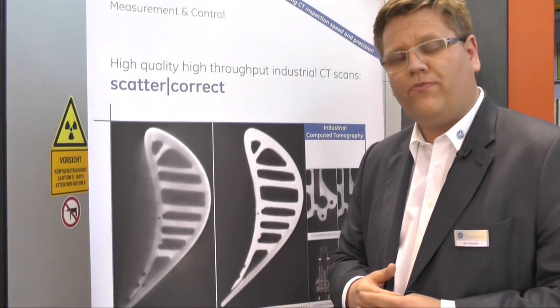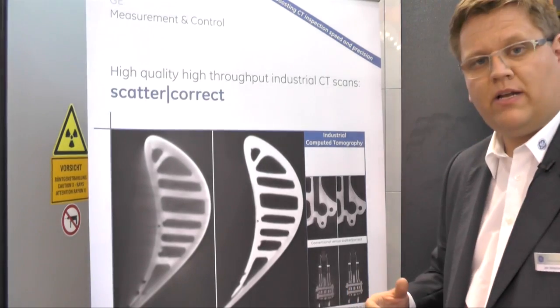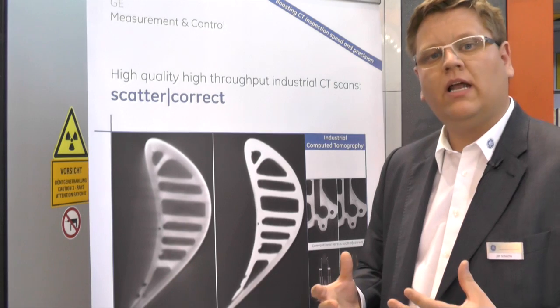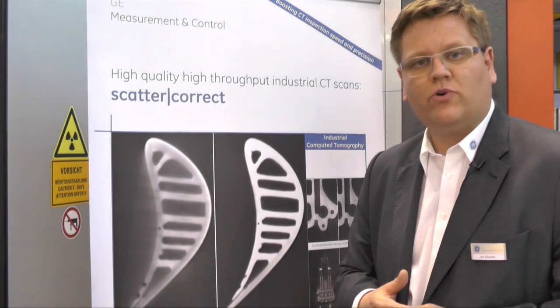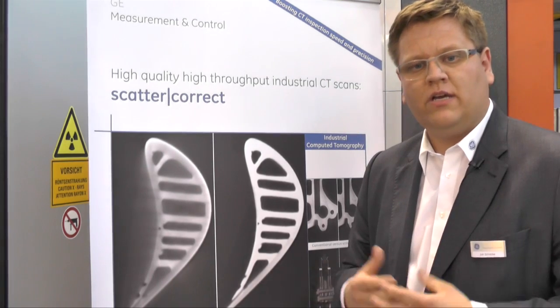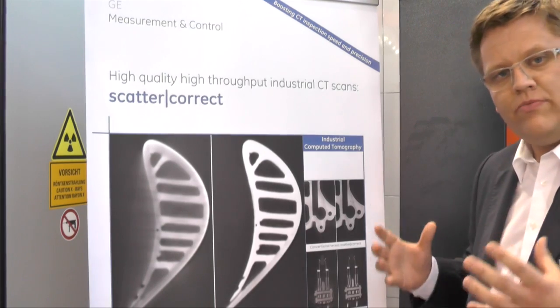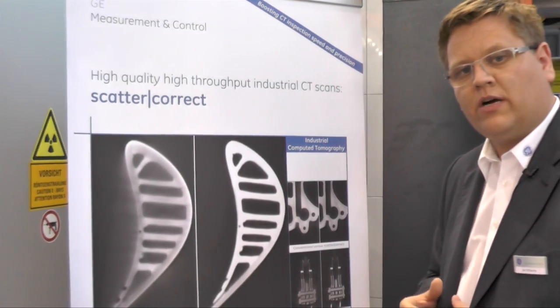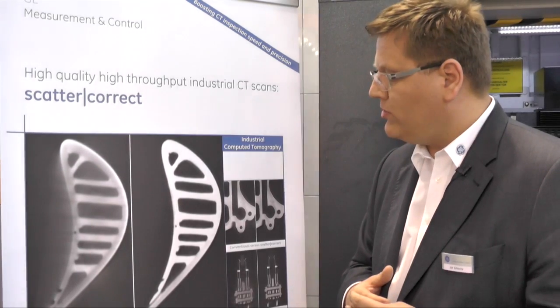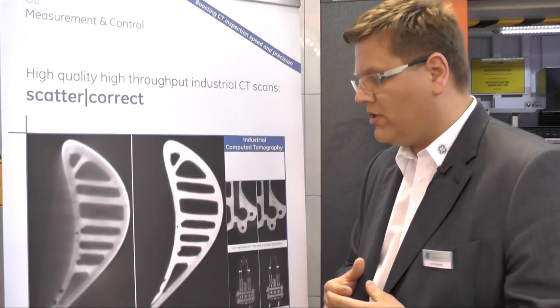In the past, you were forced to take a line detector instead of a flat panel detector in order to get a sharp result. However, using a line detector takes much more time compared to a flat panel detector. Therefore, GE is in 2015 introducing ScatterCorrect, a hardware module which is used together with a certain software module in order to reduce the scatter radiation for a cone beam CT.